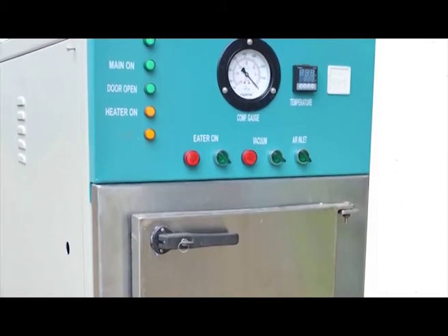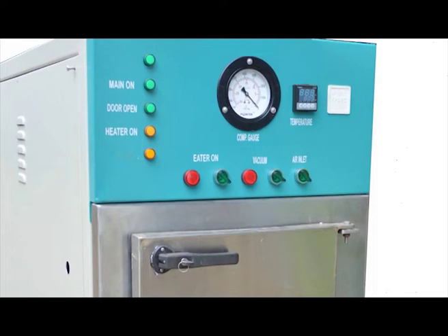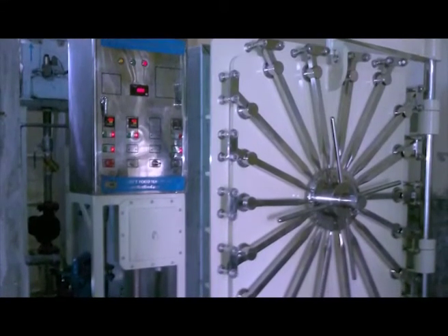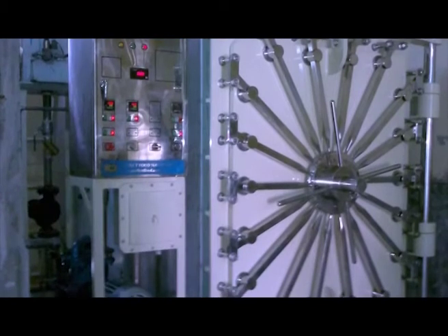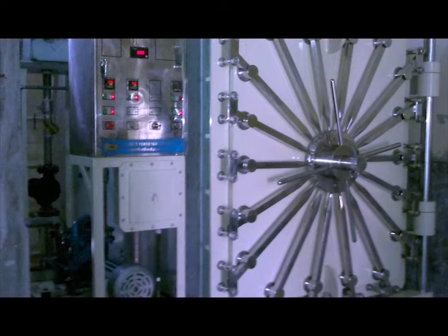This moist sterilizing process requires a period of post-sterilization aeration to remove toxic residues. Because ethylene oxide is toxic to humans and other animals, the item sterilized with it must be aerated before use to allow the gas to dissipate.